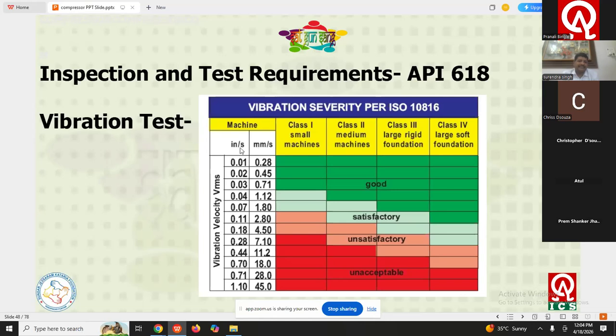On the left side you can see this is inch per second. So this is a conversion. If you are measuring in inch per second, that is 0.01. So this is basically the acceptance range for class 1 for my compressor. For class 4, my acceptance range is up to 2.8. Okay. Now, if my compressor vibration is coming to 11.2 for class 1, it means I am in the red zone. If I am in the red zone, I immediately need to overhaul my compressor, take a shutdown and go for reholing, overhauling.